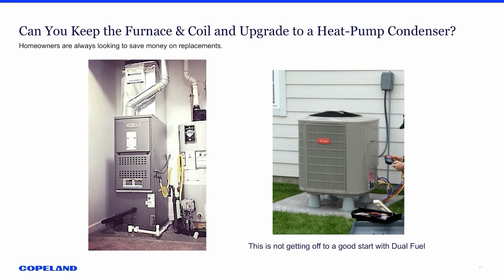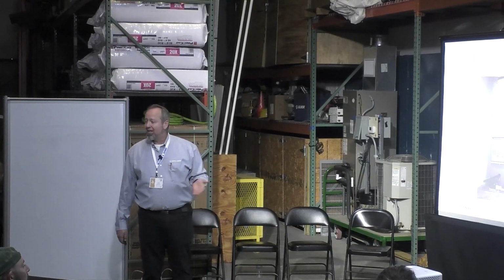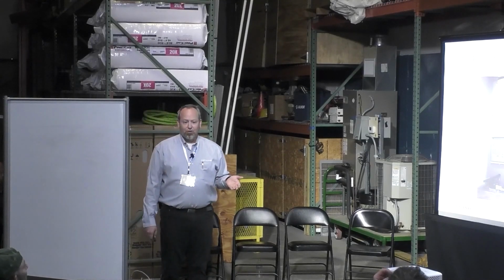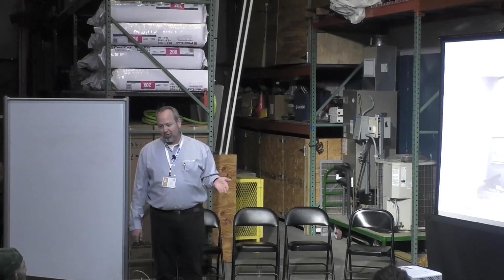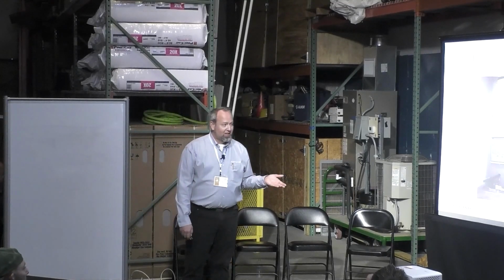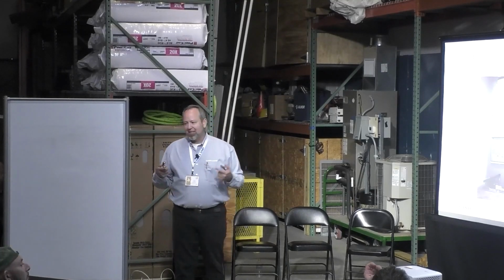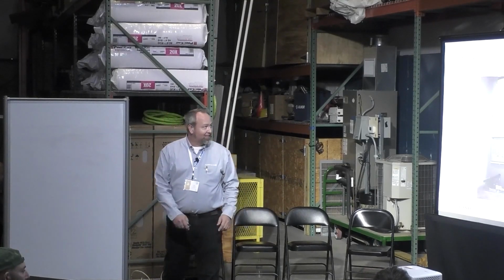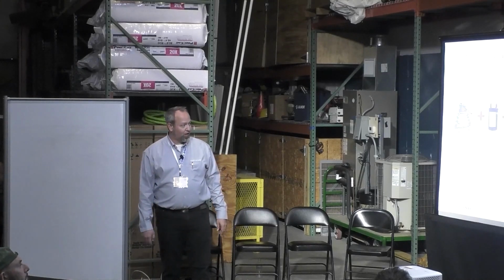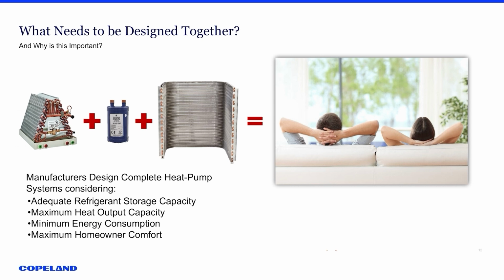Now, there is one thing to keep in mind with this, and you'll notice that on this, it is a downflow. So the coil is on the outlet side, and we're going to get to talking about that in a little bit. But when a homeowner is looking to save money on the replacement, they're not looking to spend it on their energy bill for the next 5, 10, 15 years. And so matching those systems, getting the indoor and outdoor matched, is absolutely necessary to make the system function and work right. What needs to be together? Indoor coil, outdoor coil, accumulator, they all need to match.